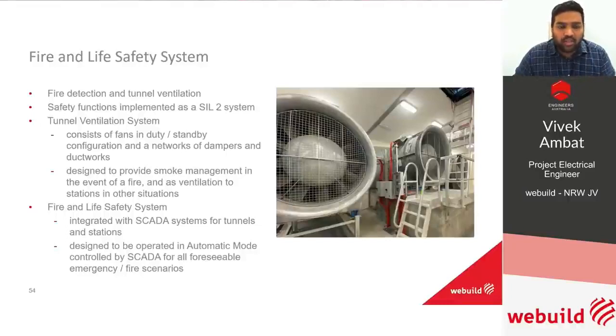So there were a few challenges with the design of the tunnel ventilation system, especially at the Airport Central Station. We identified through the CFD modeling for smoke scenarios that the originally designed position of the exhaust would have caused smoke to hinder the evacuation pathways and, more importantly, affect the control tower, which was located next to the Airport Central Station.